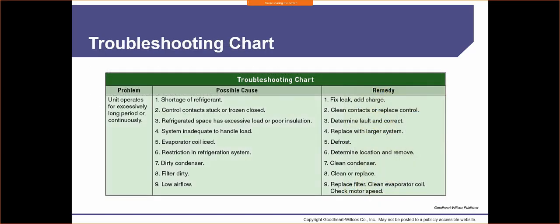And so here's just another version of that troubleshooting chart that we talked about earlier. Just to go quickly over the sequence of operation, if you don't already know, I don't know if I have a slide that covers it, but just to make sure: when we're talking about a furnace, there's a general startup procedure before the furnace starts running. It varies from manufacturer to manufacturer slightly on startup.